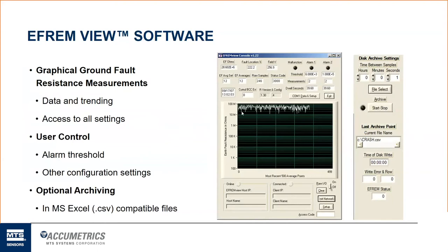It's going to appear as sort of a scatter, because again, it's not able to measure accurately any resistance values over that 500 k-ohm. It's just going to look like a massive open circuit. So it's toggling between, in this case, about 10 megohm and 100 megohm. When this resistance starts to drop and gets below that 500 k value range, it'll become a much more linear plot, and you'll see the graphic interface really start to show the resistance more accurately. So again, the customer should not have any concerns. This would be a healthy rotor. This is what we would normally expect to see, that scatter pattern up above, at least 1 megohm. Usually, like I said, on a good rotor, it's that 10 to 80 megohm range.